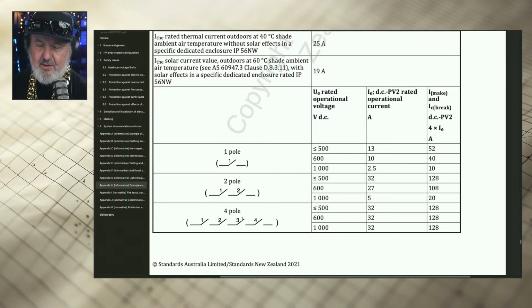And Wrigley says, I noticed some commercial installs that have the inverter enclosed in a stainless steel enclosure. Does this change the rating as it's not strictly directly exposed to sunlight? If the inverter has an inbuilt DC isolator and it's tested to 4777 Part 2, it would need to meet those thermal ratings. But if you're installing one yourself as an external DC isolator, you'd need to ensure that if it's indoors and enclosed, there is a rating. And if it's outdoors, even if it's enclosed, if it's exposed to sunlight it's still considered solar affected, because the sun's going to heat up that enclosure.